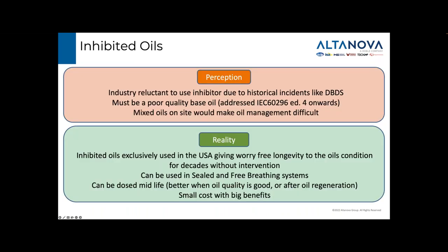In the UK in particular, we have been reluctant to use inhibitors due to historical incidents like DBDS, or dibenzyl disulfide, or the presumption that the base oil was poor quality before the inhibitor was added, or concerns over having to manage multiple oil types. In reality, however, some countries like the USA only use inhibited oils from installation of the asset. This saves money by reducing maintenance intervention over the oil's lifetime. It can be used in sealed and free breathing systems and can even be dosed mid-life. However, if this is done, the oil should be in good condition to begin with. If it's aged, then the oil should be regenerated prior to inhibitor addition, because the regeneration process will take the inhibitor out of the oil.